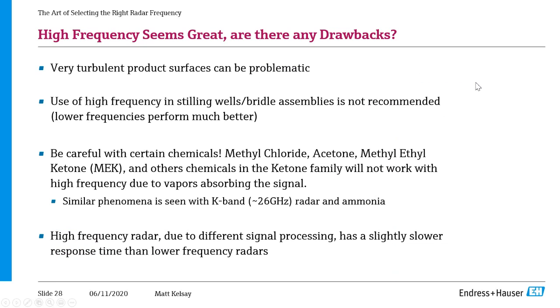Okay, so this high frequency seems great. Are there any drawbacks? Yeah, there are a few. The first one, and probably the biggest, we already talked about, and that's turbulent surfaces. Again, we can use high frequency radars in these applications. You just need to look at it as a whole, look at the dielectric, look at the installation conditions, and make sure that it's a good fit. The use of high frequency devices in stilling wells or bridle assemblies is not recommended. In this case, lower frequencies or guided wave will perform better. Based on our testing, these high frequency radars have a lot of signal noise when installed in this way, so we don't recommend it.